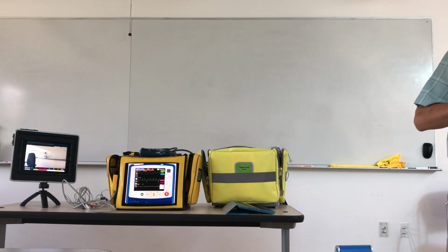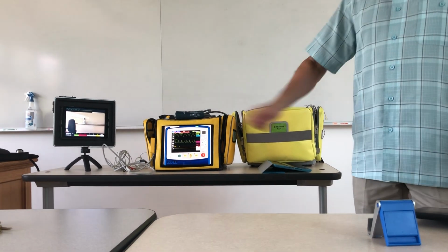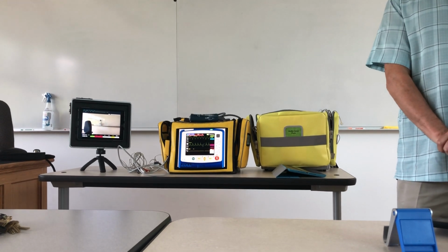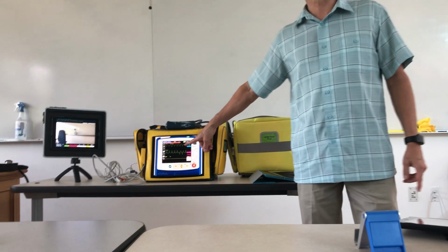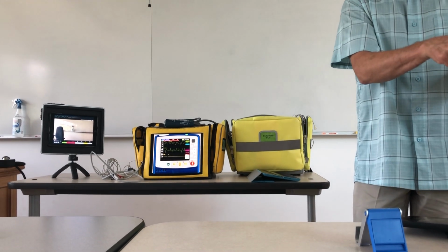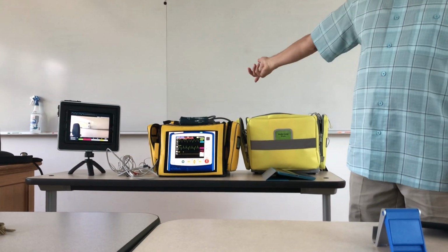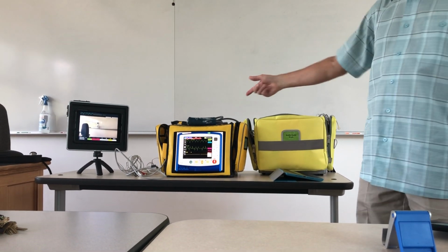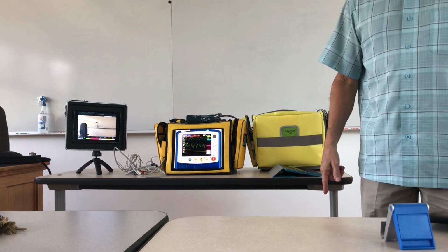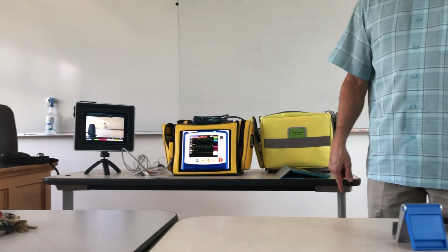That would make sense. Otherwise, what's the point of having somebody wear a sensor if it doesn't hook directly in? Well, it links up, it shows you the CPR performance. What I was saying is, I don't know if it'll change the ECG tracing, because by hitting the CPR button on the controller, it changes it to make it look like someone's doing CPR at whatever rate you've set your CPR protocol at. On the Philips, it has a CPR monitoring performance waveform. So that's probably what that's used for.